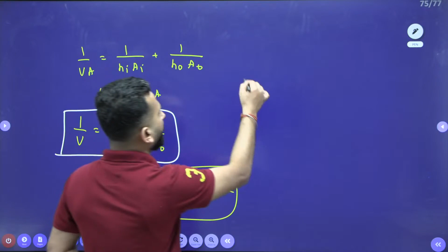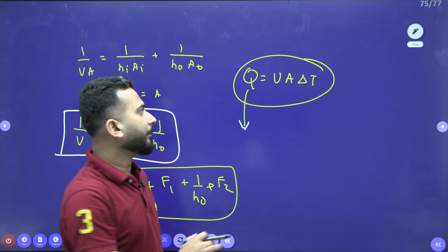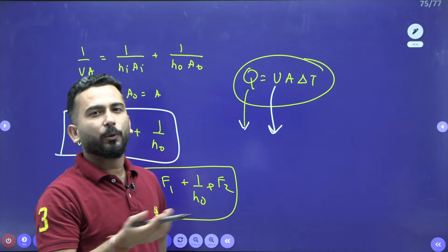And finally, what you can do is Q equals UA delta T. Now tell me one thing, see, Q value I can very easily find out by seeing which fluid is getting heated or cooled by what temperature, m Cp dT. U value I am saying they will generally give; fluids are given, so hi, ho is fine, so I can calculate U. A value I need to find out. See, my objective is to find the size of the heat exchanger, so A value I need to find out.